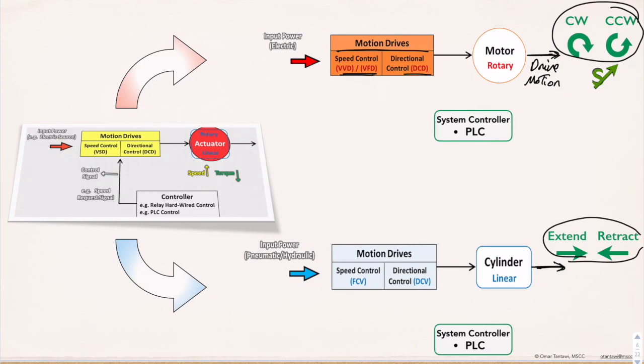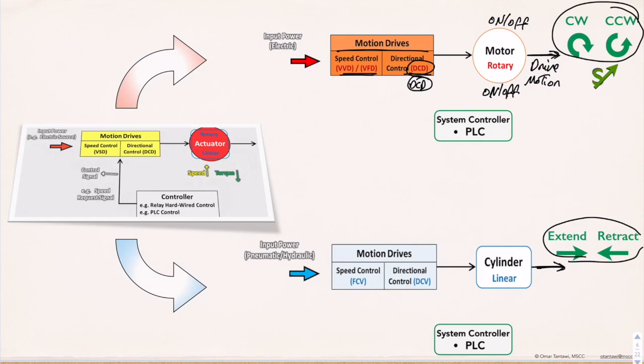If we want only to switch the motor on or off, running it in one direction, then only one direction control drive or contactor is used. If we want to switch the motor in both directions — clockwise or counter-clockwise — then two direction control drives are used. If we want to change the motor's speed, only a variable speed drive is used. If we want to turn the motor in either direction and change its speed, two direction control drives and one variable speed drive are used, and the system controller will have three control signals going to the motion drives block.